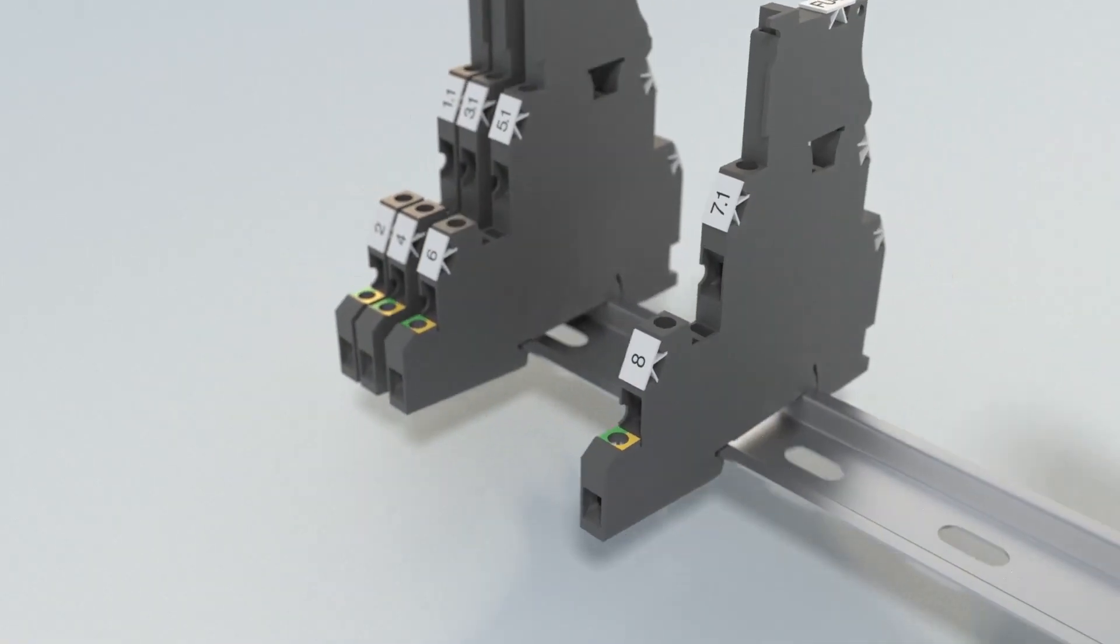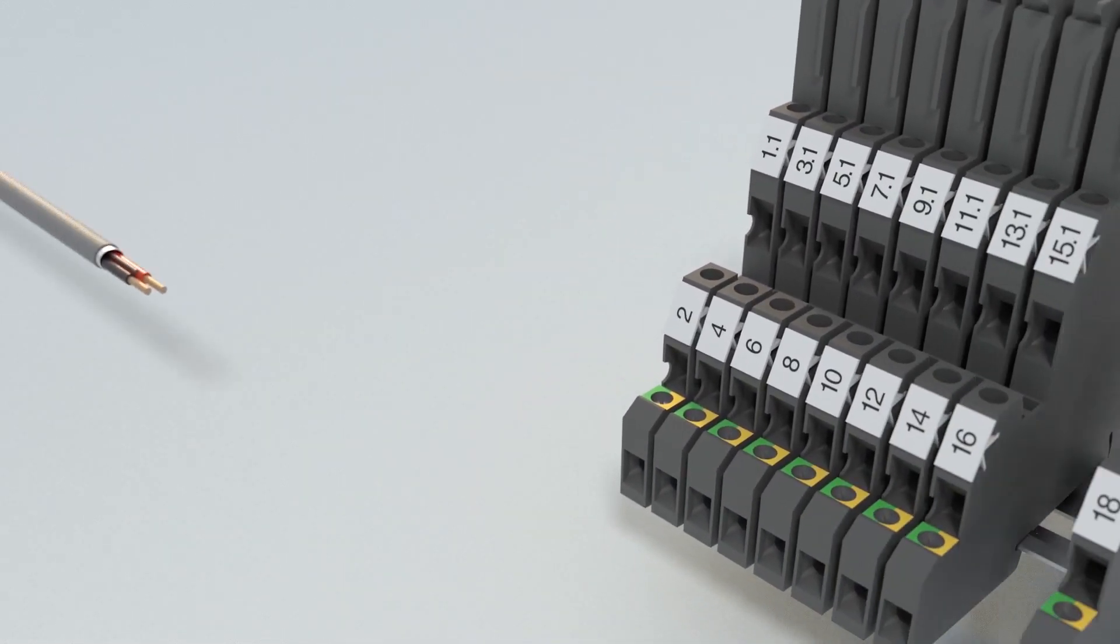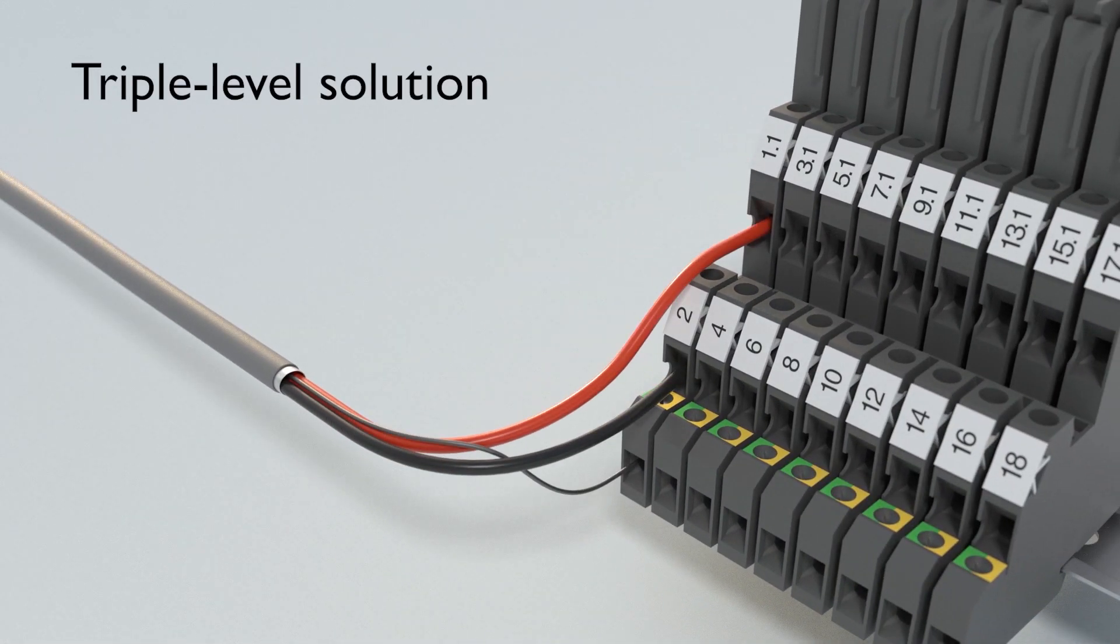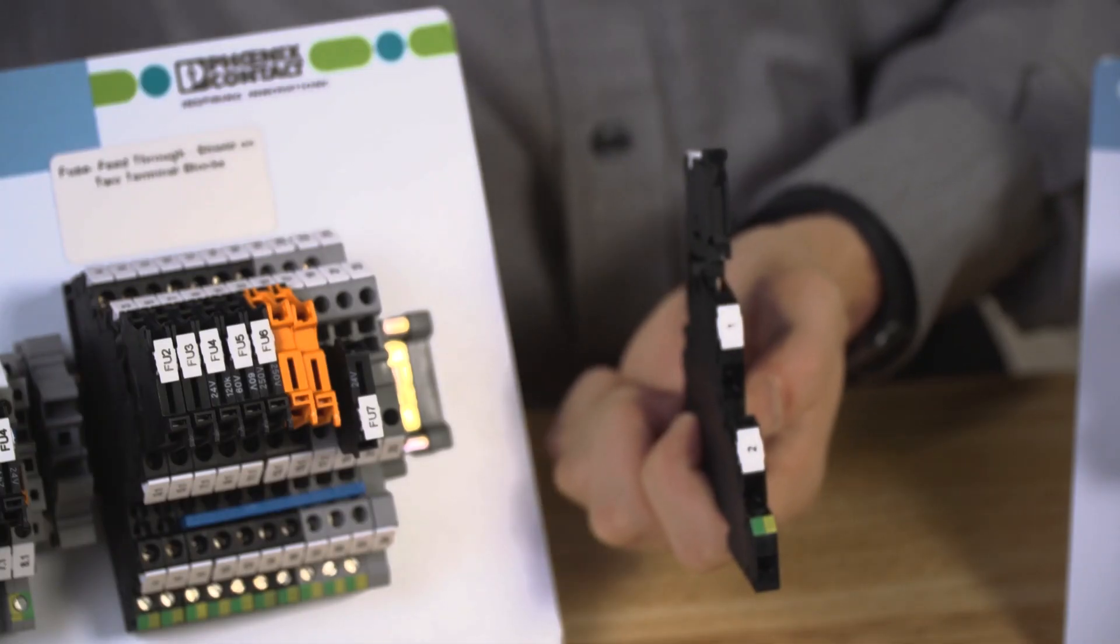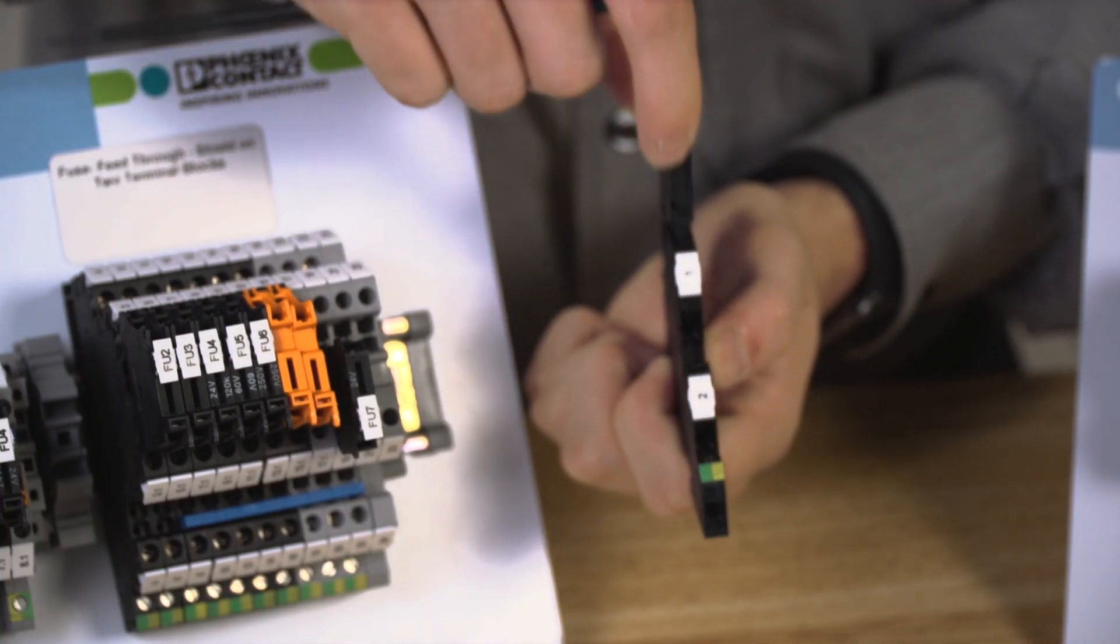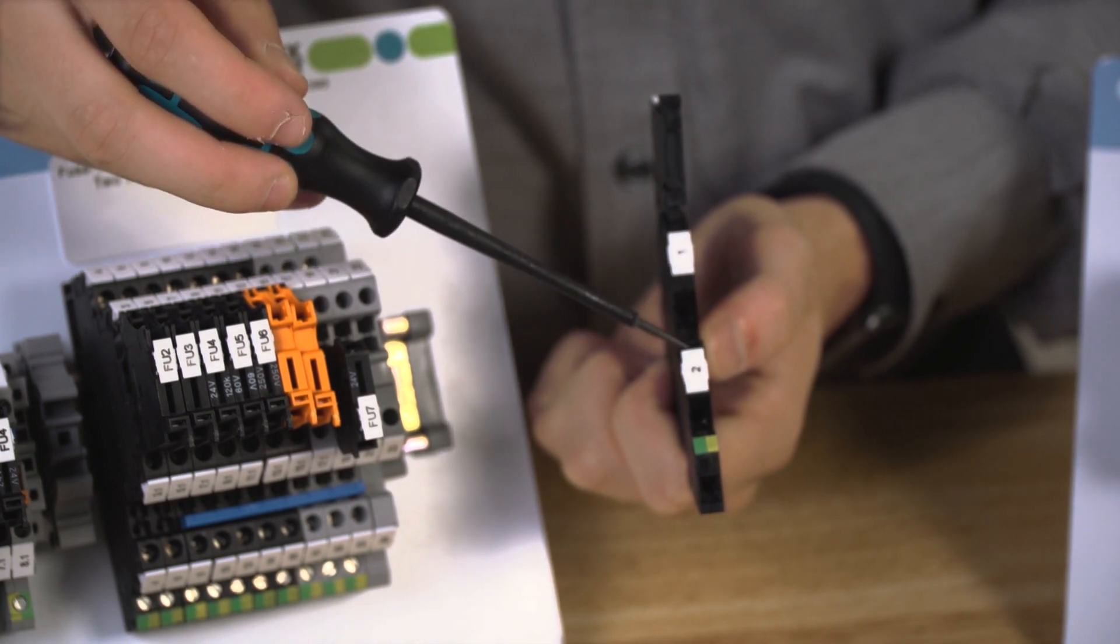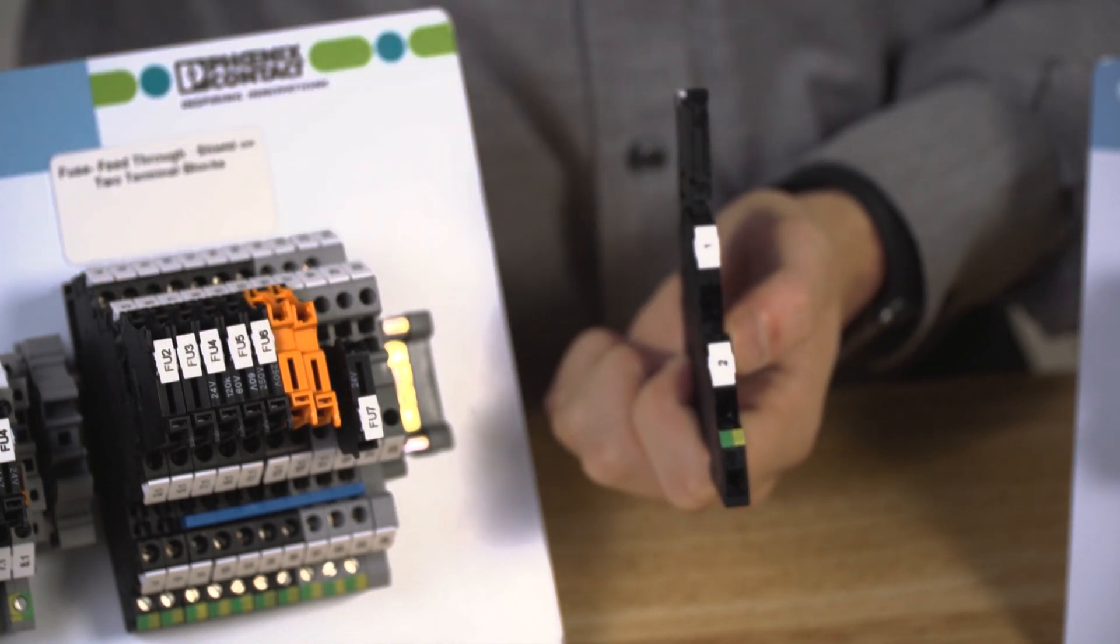To complete this family of process terminal blocks, Phoenix Contact introduced a three level block with a ground foot. These blocks incorporate a top level fuse or disconnect function with the feed through second level and a ground foot for shield connection. This configuration perfectly organizes each wire of the signal loop into one terminal block while effectively saving 66% of real estate along the DIN rail.